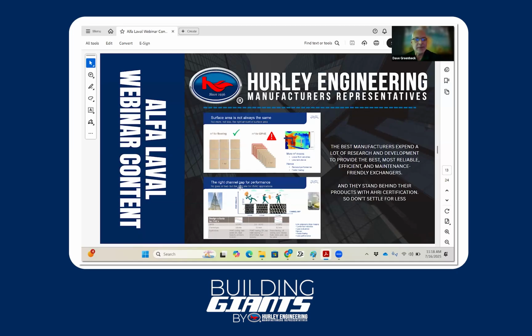So this slide is illustrating the fact that more is not better. There's the performance on a plate, and we'll go through all the variables that lead to more performance, less pressure drop, these kinds of things. And the plates just add capacity, but you don't add a bunch of plates to solve your capacity problem, because then you can go into a situation where you have low velocities with less turbulence, which produce fouling faster. And that reduces your performance and has you having to clean them more frequently.